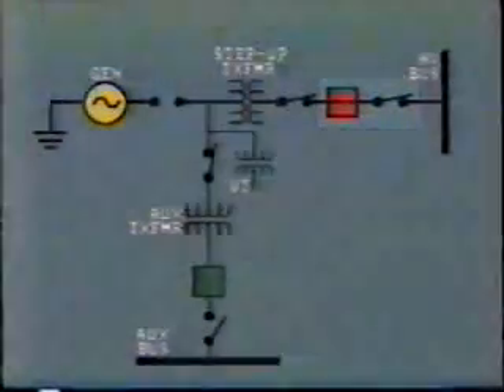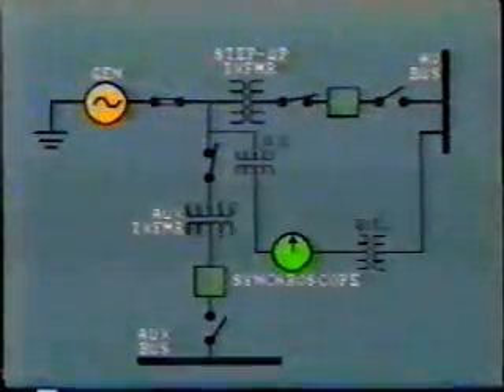Another method is to shut down the generator, open the terminal links, and backfeed the VTs by energizing the unit transformer from the high voltage side. Compare VT phasing and sequence to a known voltage, and with readings taken with the generator energizing the VTs. It's most important to make sure that the synchroscope is receiving correct information. It must be connected correctly to the VTs on either side. Remember, there will probably be a phase shift across the unit transformer, and this will have to be taken into account by the synchroscope connections.